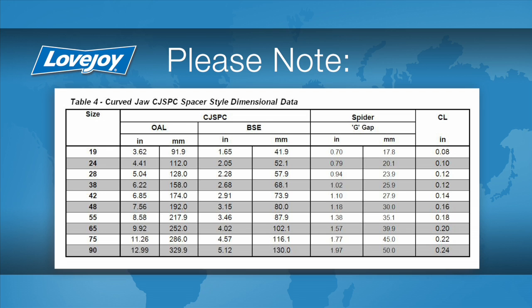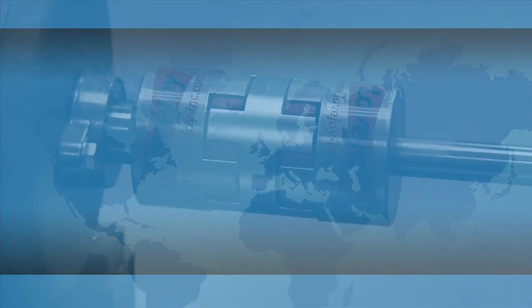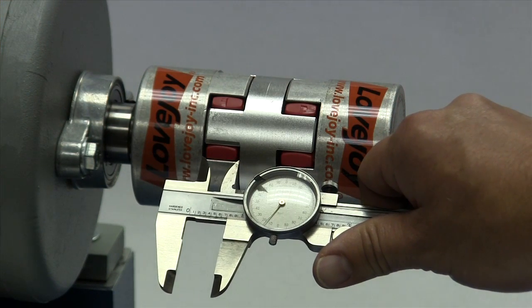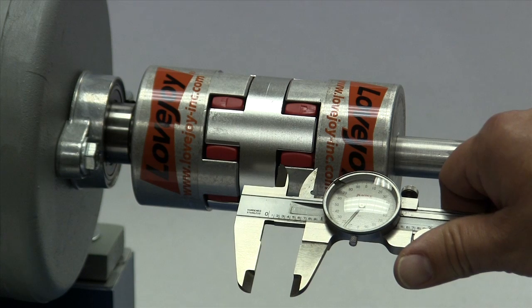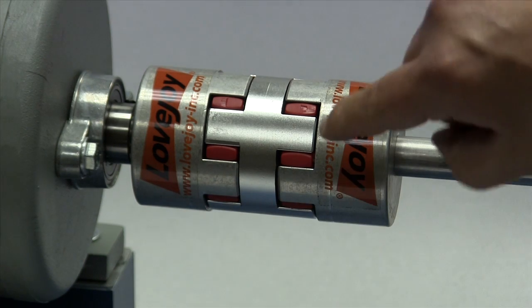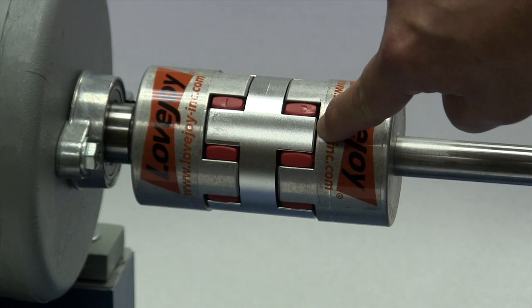The gap between the hub face and the face of the spacer can also be measured and should match the G or gap dimension within plus or minus 1/64th of an inch. The CL dimension is the clearance between the end of a jaw and the face of the opposing hub.